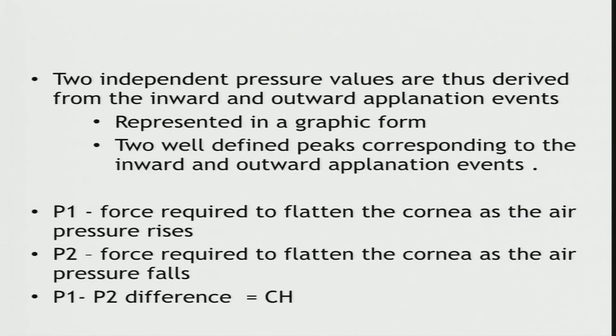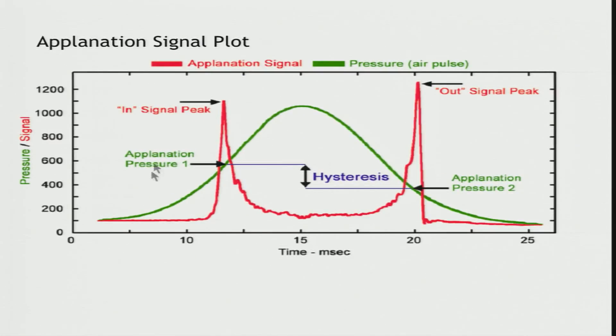These two independent pressure values derived from the inward and outward applanation events are represented in graphic form as two well-defined peaks, designated as P1 and P2, and the difference between these pressures is what we call corneal hysteresis. This is how the plot looks — the inward pressure as the air puff causes applanation, then the pressure goes down, the cornea goes into concavity and comes back to the applanated level which is P2, and the difference is the hysteresis.